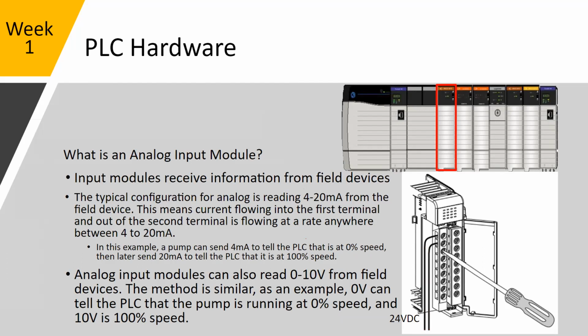So input modules, again, receive information from the field. The typical configuration for analogs is 4 to 20 milliamps from the field device. This means that there's current flowing into one terminal of the input card and out the second terminal, so it has to complete a circuit. 4 to 20 milliamps is used for analog devices. So this is going to be something that's not discrete.